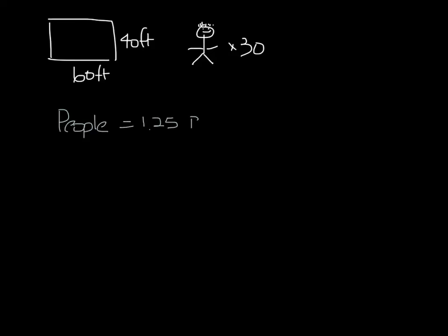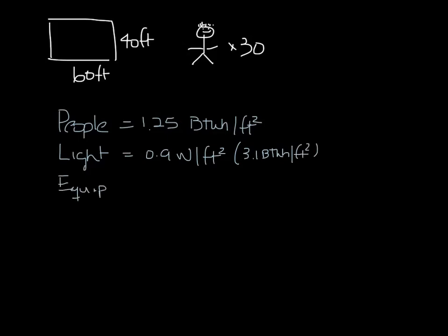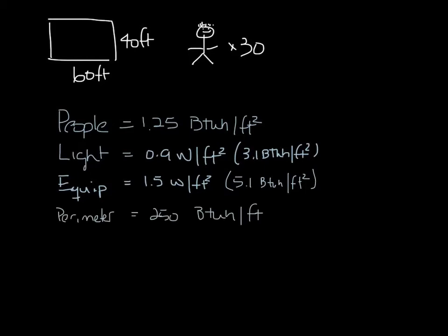1.25 BTU per square foot for people. Lights add 0.9 watts per square foot, which is 3.1 BTU. Equipment, like computers, copiers, etc., 1.5 watts per square foot, which is 5.1 BTU per square foot. And a 250 BTU per foot perimeter load, which comes to 13.6 BTU per square foot.